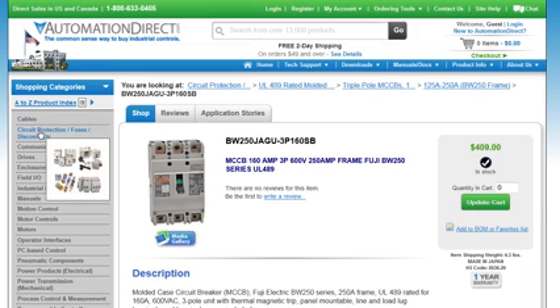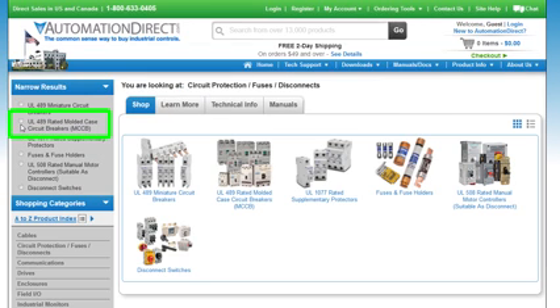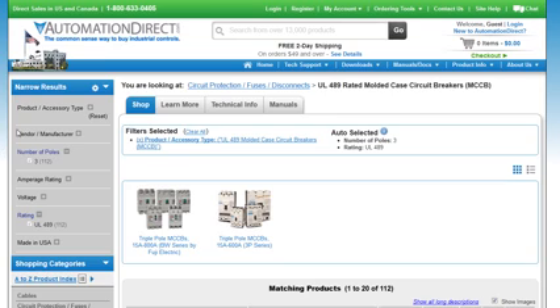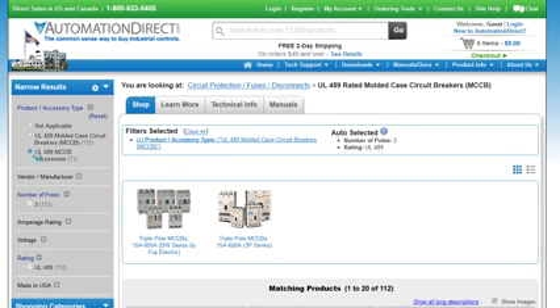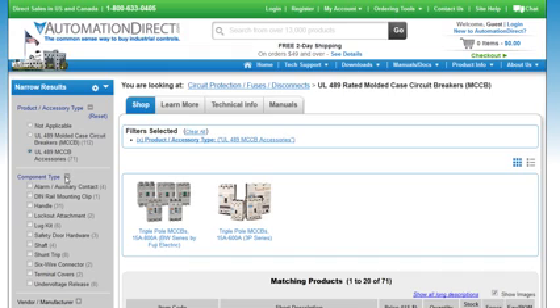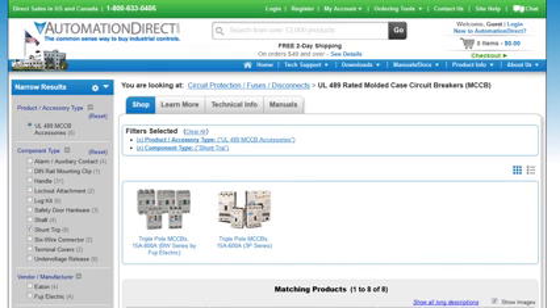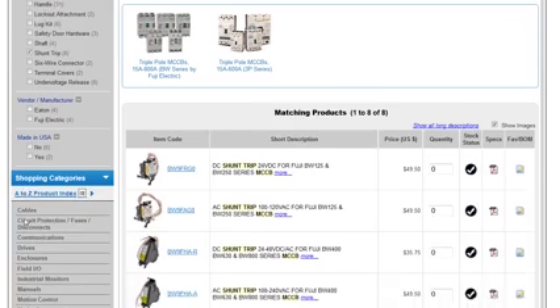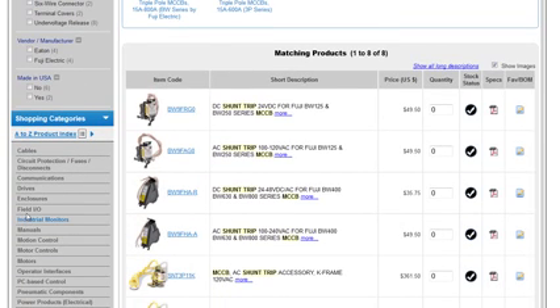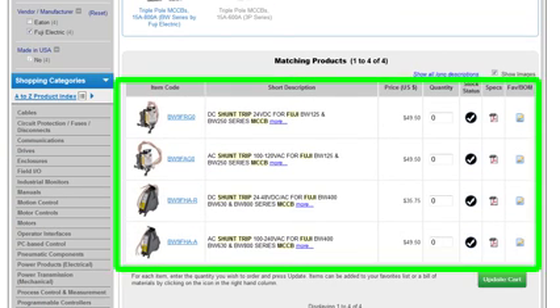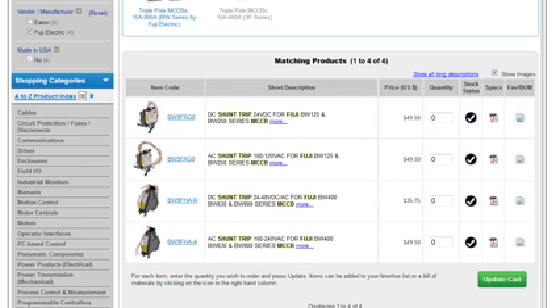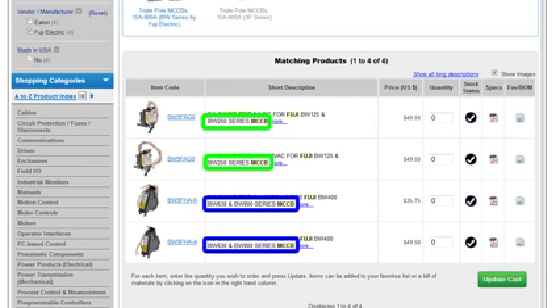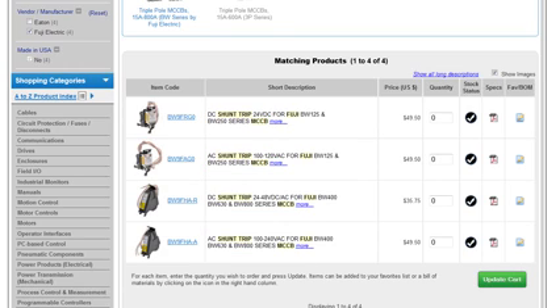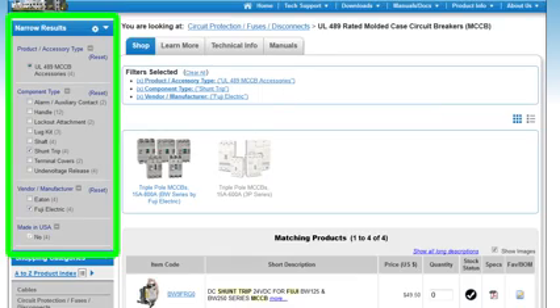The other way to do it is to come back over here, select MCCB, and this time choose Accessories, and then I can select the component type I want. Let's do a shunt trip, for example, and select the type of breaker I'm using. Let's assume we selected a Fuji, and all of a sudden we're down to 4 possible part numbers, which we simply match up with the series of breaker that we're using, in this case a 250 or 630, and whether we want 24 volt or 120 volt AC control. This parametric search makes selecting circuit breakers and accessories so easy.